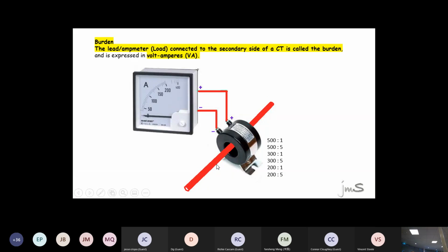Now look at this one. 200 to 1. Which one are you going to choose? 200 to 1. But guys, if you choose a 500 one, it's not true that the needle will go to 500. It will only go to 200 anyway. It all depends on which ratio you choose. So if I say 1 amp, there will be 1 amp on both sides, and then what will this show? Also 200. This is not the most common one, but you get the 5 amp one, which is most commonly used.